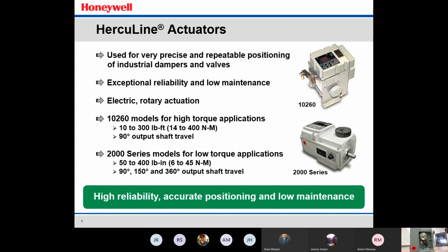The Herculine actuators are used for precise control, repeatable positioning of industrial dampers and valves. It has exceptional reliability, low maintenance. These actuators, in some cases, have been out in the field for 20, 30 years. In the case of the 10260, we have these actuators in a lot of very harsh environments. These would be including in steel mills, sometimes in concrete manufacturing, limestone operations. There's been several times where I've walked out into plants and the whole actuator is encased in limestone, and you can't even see the actuator, but it's still moving, still doing its thing. So these do operate in some very harsh environments.